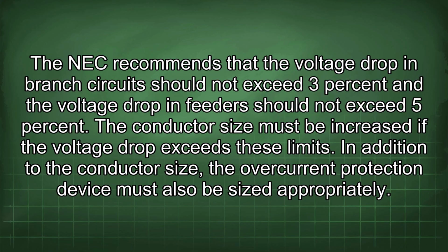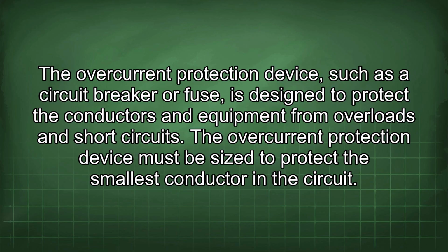In addition to the conductor size, the overcurrent protection device must also be sized appropriately. The overcurrent protection device, such as a circuit breaker or fuse, is designed to protect the conductors and equipment from overloads and short circuits. The overcurrent protection device must be sized to protect the smallest conductor in the circuit.